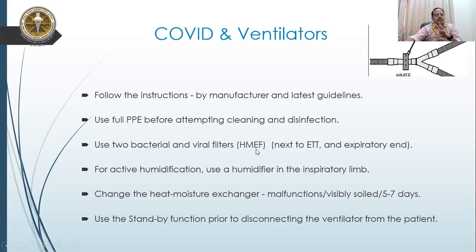These are essential so that you prevent contaminating the patient as well as the ventilator. Active humidification also reduces chances for infection, so that has to be used, which I have already discussed.